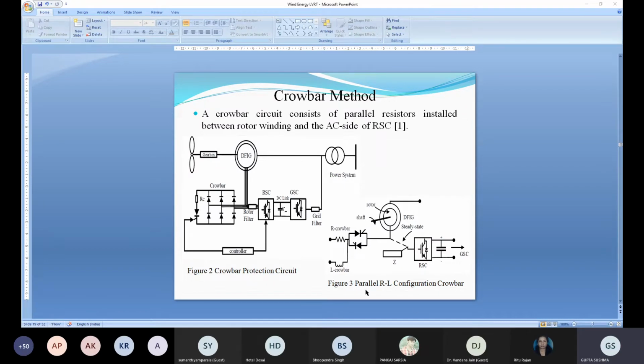So overcurrent will be protected. Z is the grid impedance. Because calculation of this rotor is very important, if we consider this grid impedance at the time of rotor resistance calculation, then we will get the accurate value of rotor resistance, crowbar resistance. So at the time of rotor overcurrent or DC link voltage, the crowbar circuit is triggered and a low resistance path is created for high current to flow. In this operation, RSC is disconnected from the rotor winding by the closed crowbar switch.